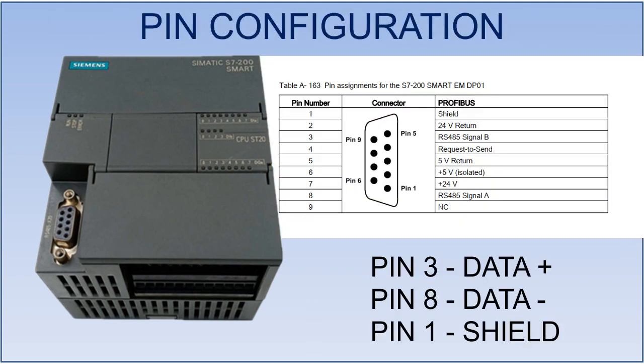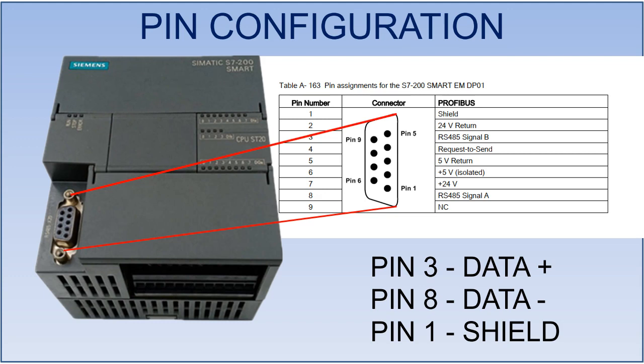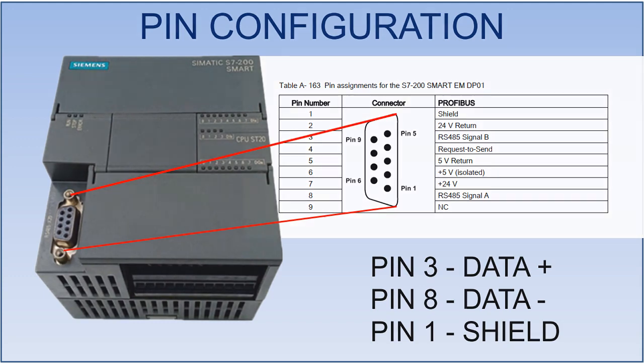Here I will configure the PLC as Modbus Master from the onboard RS-485 port. A 9-pin D-type male connector will be required to connect with the female port on the CPU. Pin number 3 and 8 will be used for communication and pin number 1 will be used for shielding.